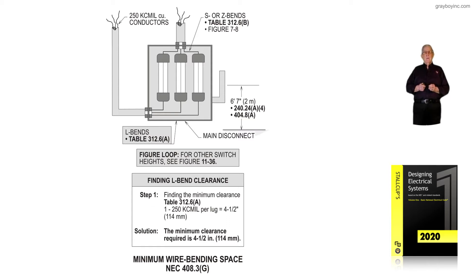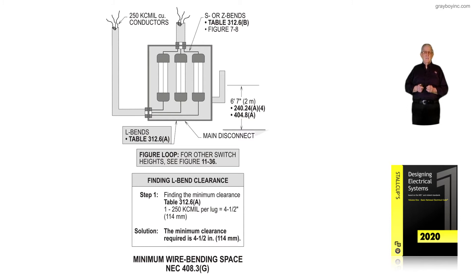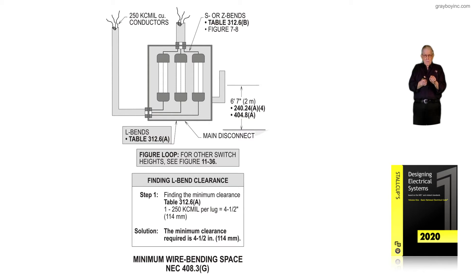Coming in to the bottom of that switch on the load side — or exiting, however you want to say it — we have 250 KC mil conductors bent in an L-bend. Electricians like L-bends because the conductor comes in an L-shape; they can pull it toward them, stab it, and they have more control stabbing an L-bend into the terminal or lug connections they are terminating to.